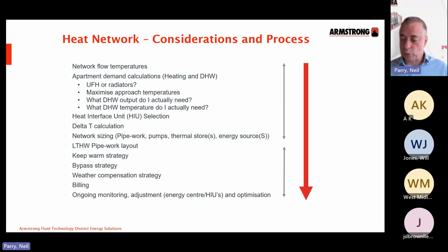So only when you've selected which HIU you're going to use do you then know what the return temperature will be, and then you have your delta T that you can use to calculate your flow rates. Moving on from that, you can calculate your network size, the pipework size, the pumps, the thermal store, etc. You can look at the layout of the LTHW pipework later on.